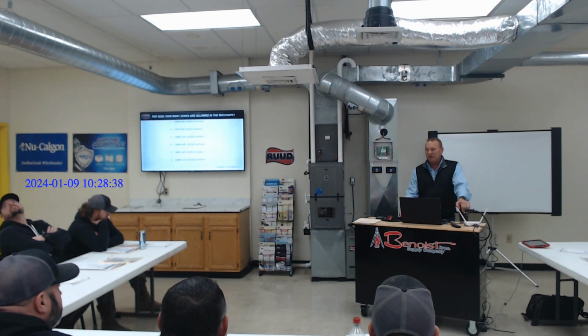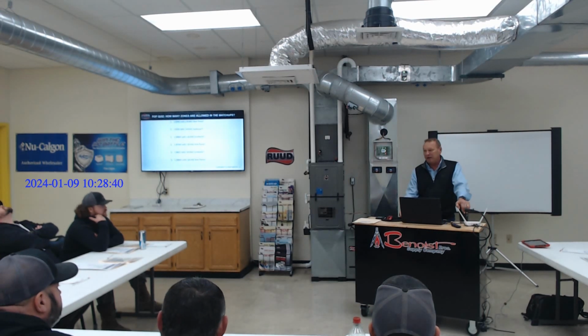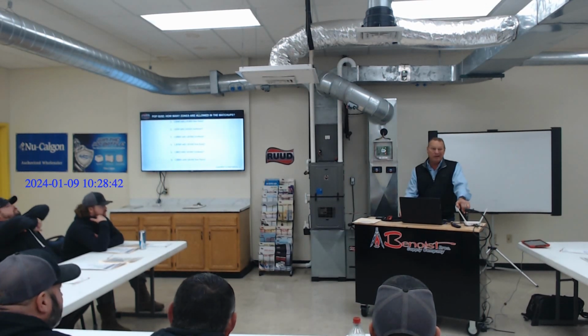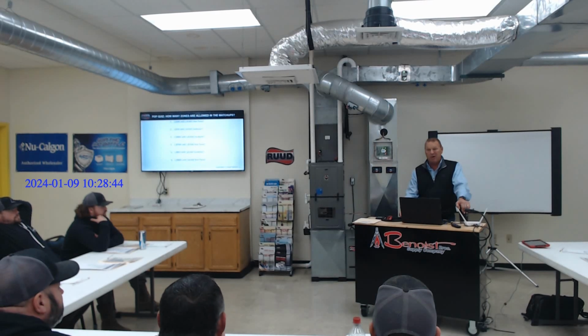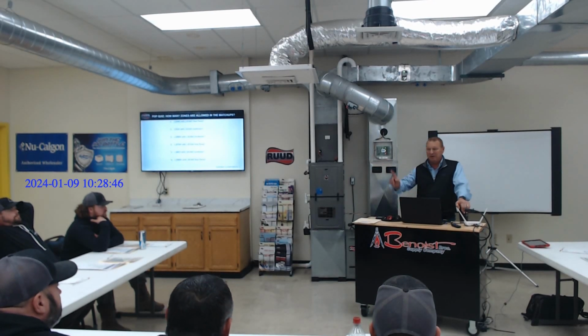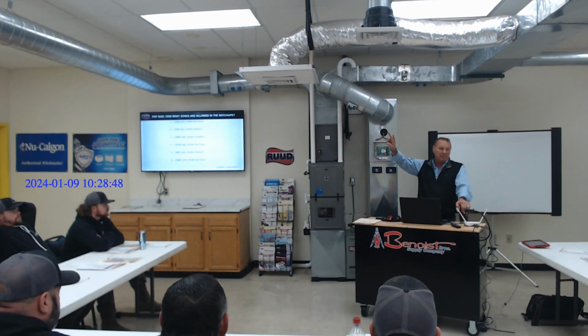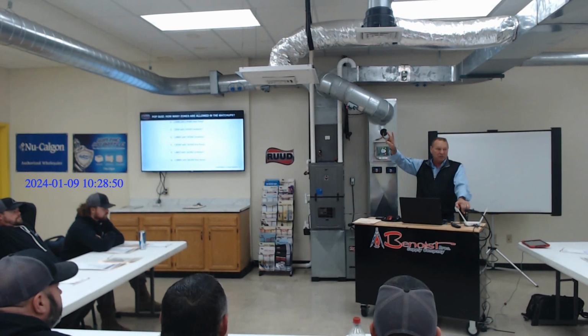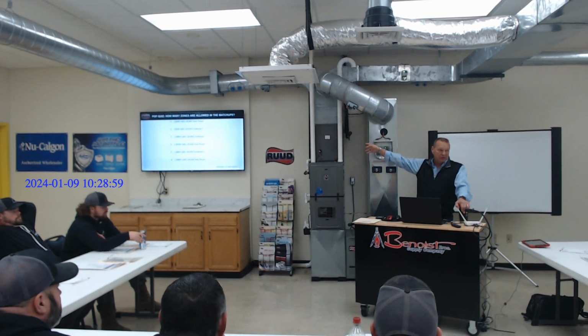Now, all our heater kits are communicating with the board. They're communicating and coming on in stages rather than all at once, or just getting an option for a W1 and a W2 like we've had in the past on generic air handlers, the regular Ruud single-stage air handlers. All our heater kits are communicating with the board. So it's going to stage electric heat on through the communicating stat instead of bringing everything on at once.